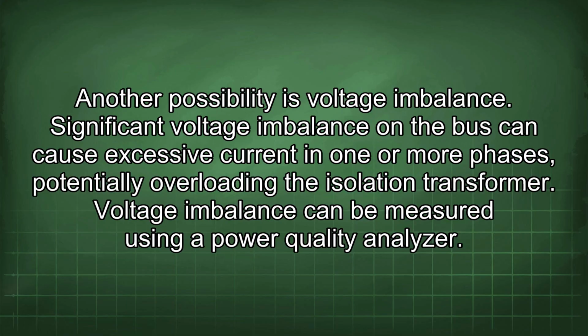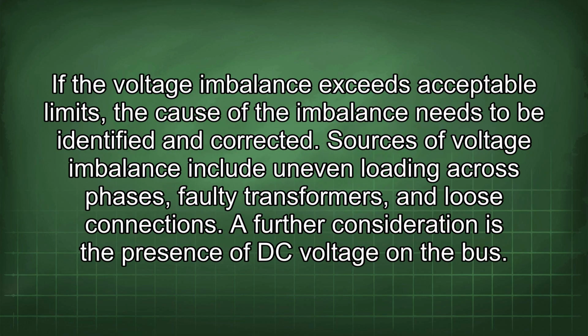Significant voltage imbalance on the bus can cause excessive current in one or more phases, potentially overloading the isolation transformer. Voltage imbalance can be measured using a power quality analyzer. If the voltage imbalance exceeds acceptable limits, the cause of the imbalance needs to be identified and corrected. Sources of voltage imbalance include uneven loading across phases, faulty transformers, and loose connections.